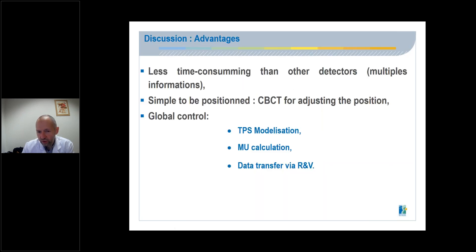What are the advantages of delta-4 phantom plus? Firstly, it's less time-consuming than other detectors, because it allows multiple information in one area. It is simple to position on. You can use CBCT for adjusting the position on the action. It's very precise. And it allows a global control. You can check the TPS modelizations, the MU calculations, and so the data transfer via record and verify.